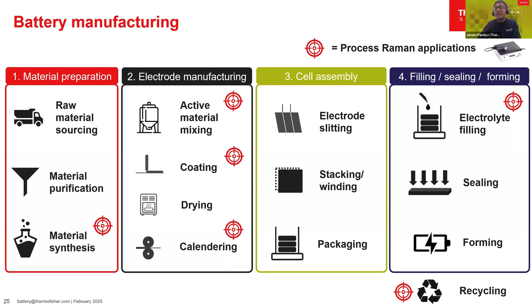Process Raman can provide real-time information in characterizing the cathode and anode material, as well as quantifying the active material concentrations. On the other hand, electrolytes are often strong Raman active materials, and process Raman can be utilized in quantifying different electrolyte components in real time during the formulation, and a flow cell will be an ideal choice here. The traditional measurement techniques often require sampling and offline analysis, which could be hazardous and unsafe. Process Raman equipped with a corrosion-resistant probe or a flow cell could provide accurate inline on-demand measurement.